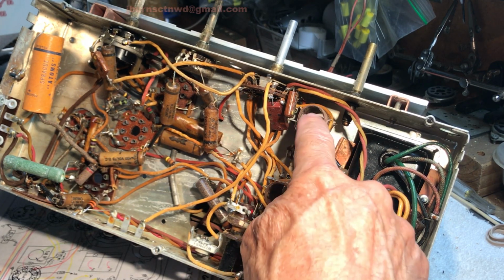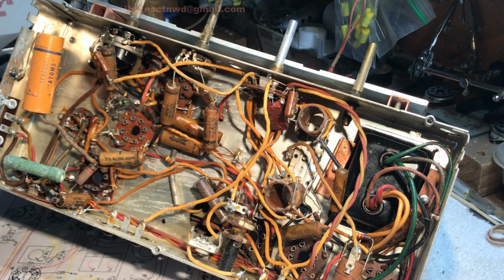Now we're going to have to check these coils here, and these coils can be a bit of a squeaker because typically there's a common ground and all the other ones loop through it. So with multiple coils on the tube, it's hard to tell exactly which ones you're measuring at any given point. If you're getting tone everywhere, well then I guess all the coils are viable. But if you don't get something across a couple of the darn things, well then I'm thinking you might have an issue there, and if you're not getting anything else, then there's a suspect coil.